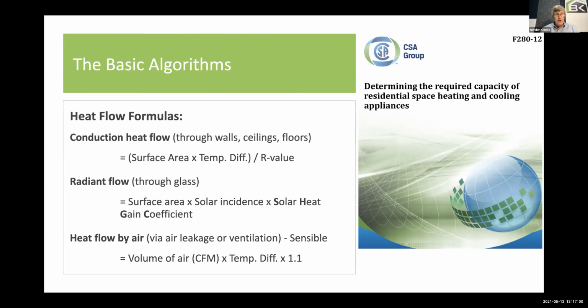So that'll be good. The third formula is heat flow via air. So think about air leakage coming into the house, or ventilation. And we're also going to use this formula to figure out how much air we need to heat a space or cool a space. But in this case, it's equal to the volume of the air, the cubic feet per minute, times the temperature difference, times this constant 1.1. And this does vary a little bit depending on where you are. If you're up in the mountains in Alberta, this number would be a little different. But this has to do with the specific heat of air, the density of the air. That's all it is. It's a physics constant. It stays at 1.1 or 1.08 depending on altitude. But you get the idea. Those are the three basic formulas, and we're going to use those throughout this session.